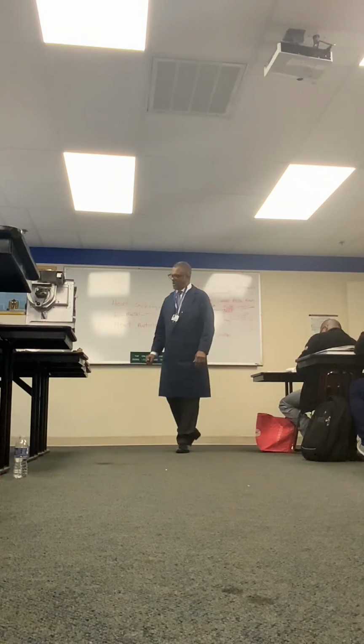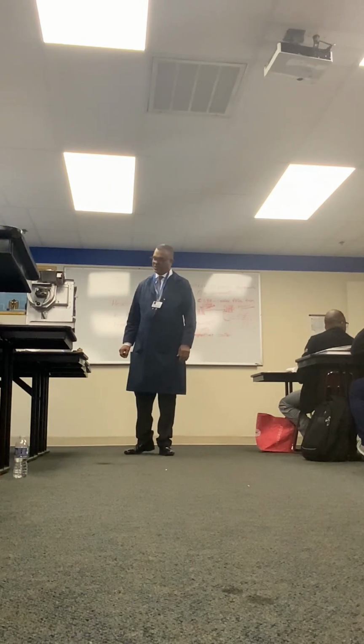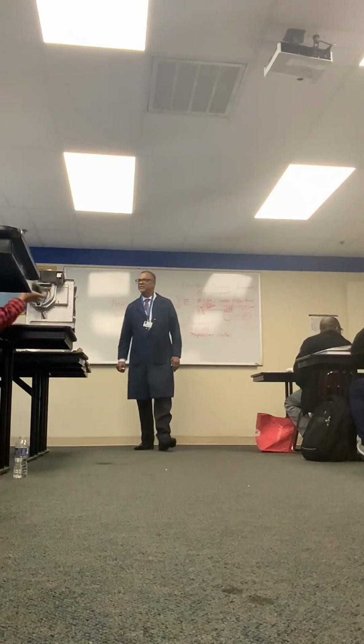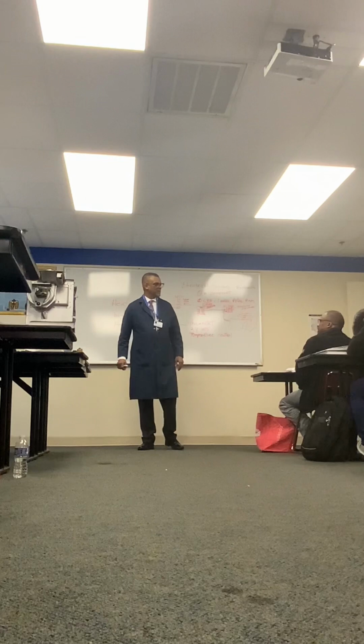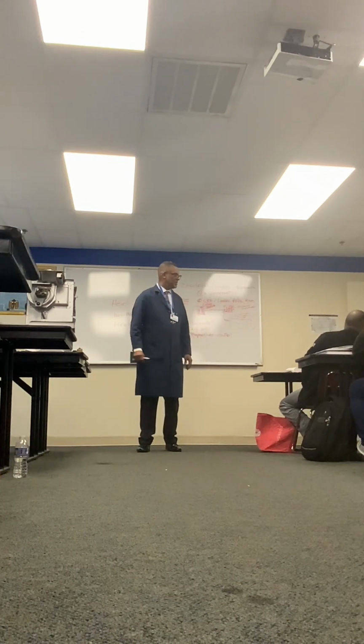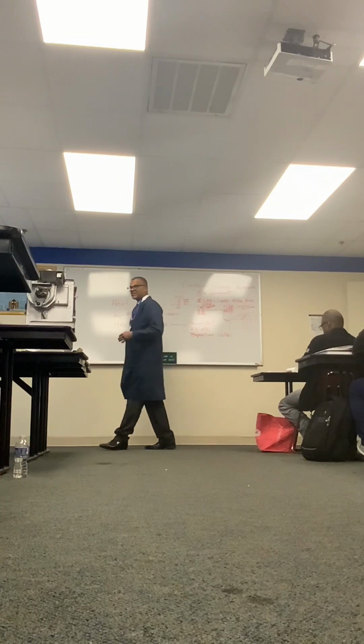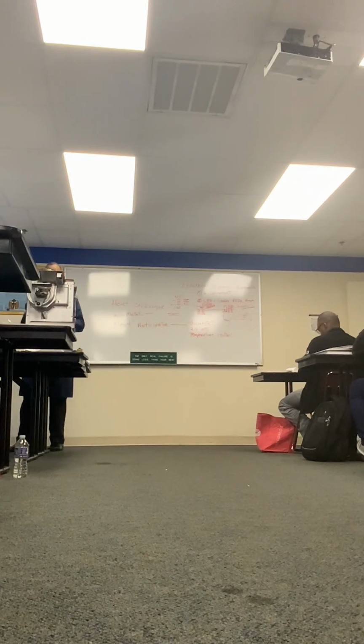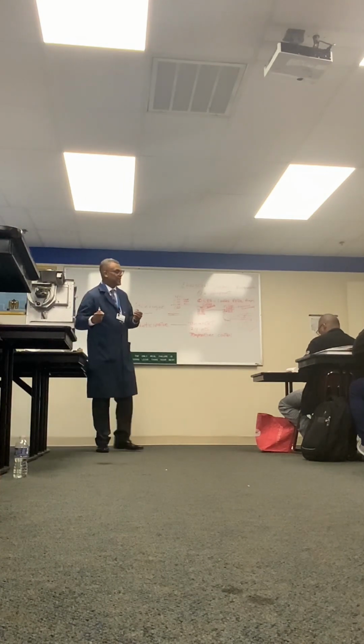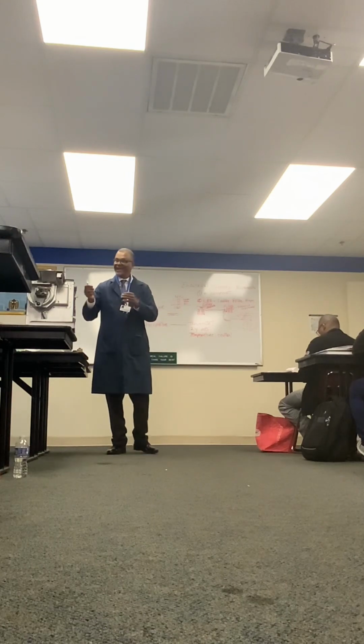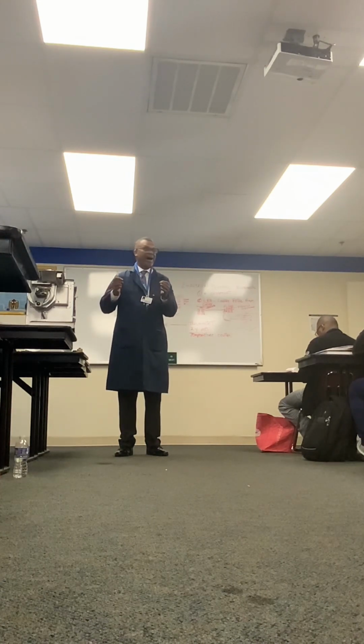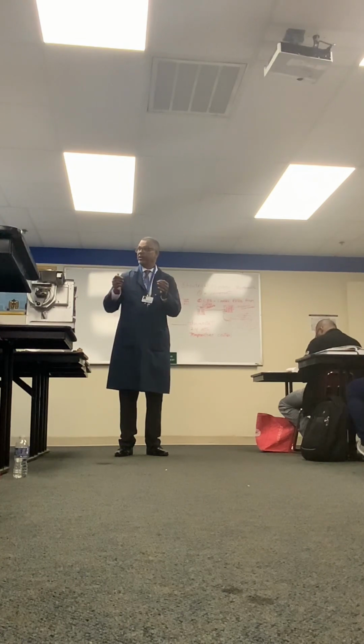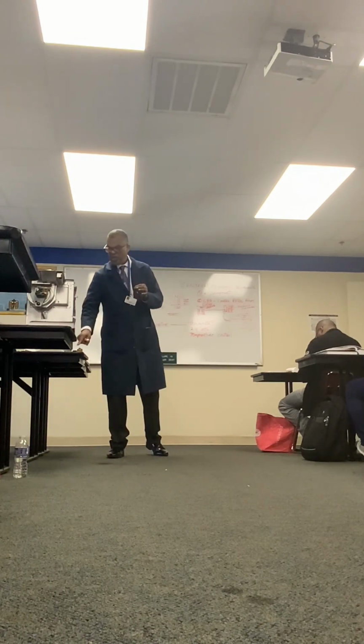The switch at the top. Yep, it's 40 amps. That's a 40 amp breaker. What's that one? 20 amp breaker, they look kinda just alike, don't they? But it's a 20 amp breaker, it's half that size. If you put that on a 40 amp appliance, it's not gonna work, it's gonna trip. Because amperage represents, to get to your question of thermal, heat. High amperage, high temperature. If we start pulling amperage to near rating, which 40 and 20, the amperage is gonna be right there.